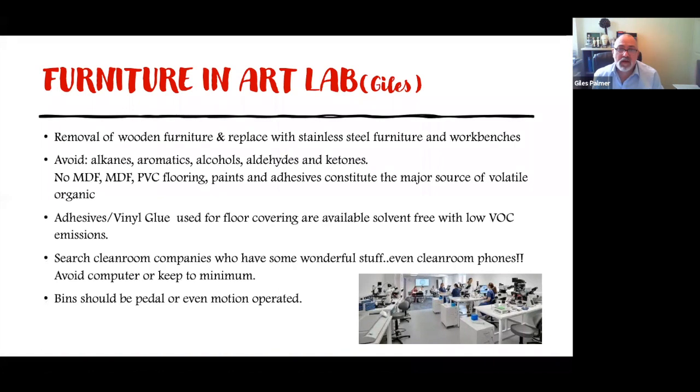Sure. Just to add on that, you have to think about whatever you're entering, whether it's yourself or the furniture, and be very sure of the materials and the VOCs which they give off. That could be the difference between a triumphant start and a very dismal start for an IVF unit, especially a new one. So it's common sense. Don't have any wooden furniture. Things to avoid are manufactured wood, like MDF, or the PVC flooring, as we've said.